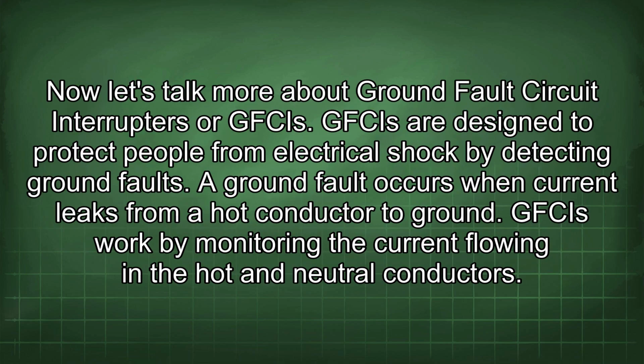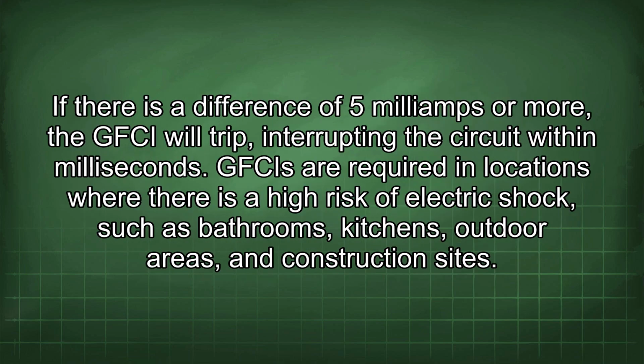Now let's talk more about ground fault circuit interrupters or GFCIs. GFCIs are designed to protect people from electrical shock by detecting ground faults. A ground fault occurs when current leaks from a hot conductor to ground. GFCIs work by monitoring the current flowing in the hot and neutral conductors. If there is a difference of 5 milliamps or more, the GFCI will trip, interrupting the circuit within milliseconds.